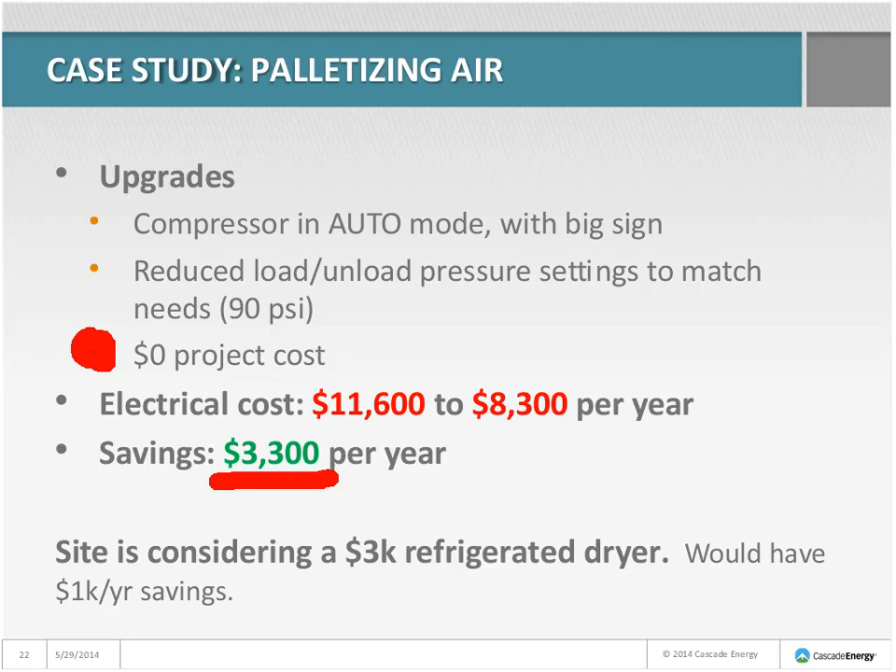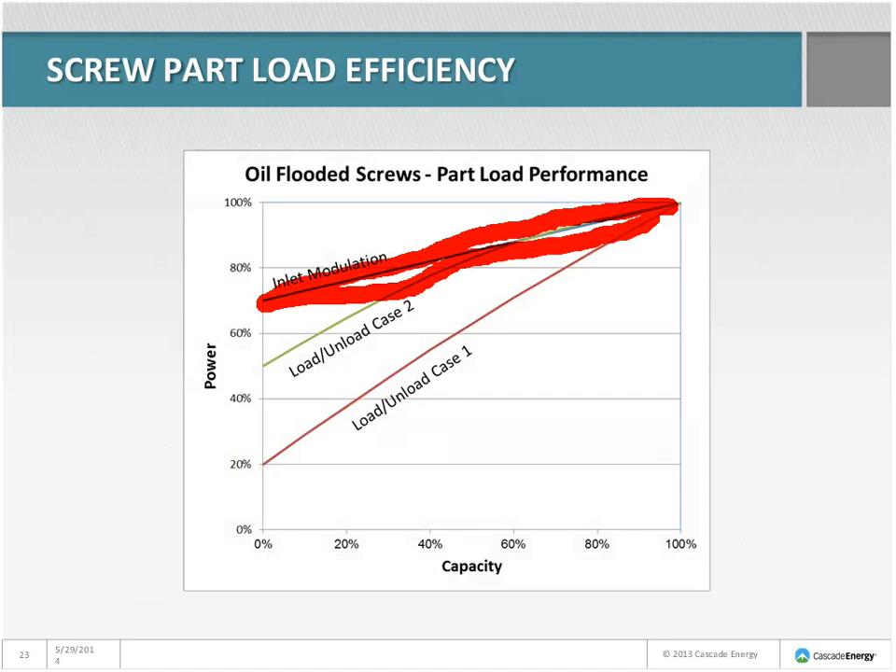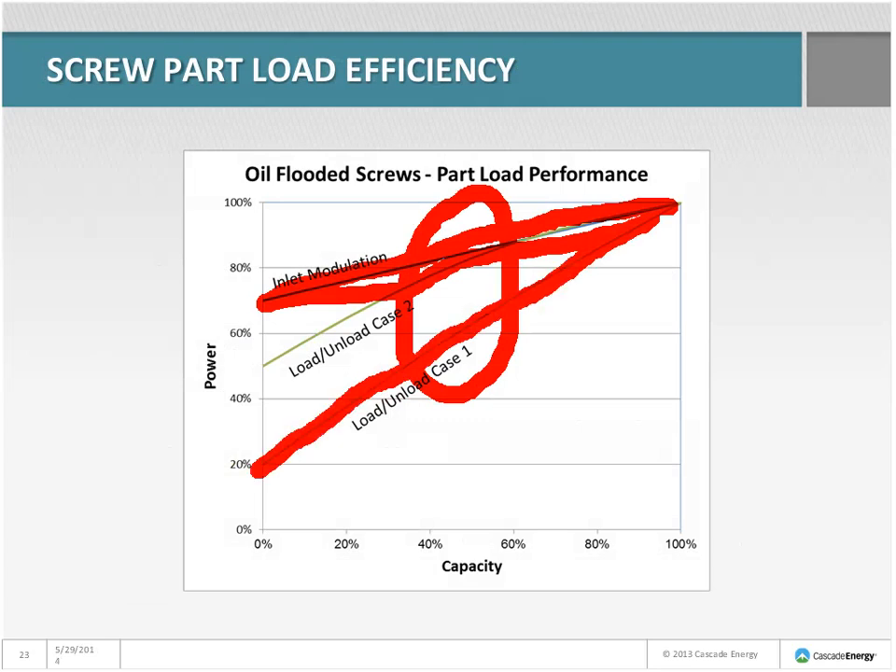These customers weren't interested in spending money but wanted to tune up the system. They put the compressor in automatic mode and posted a sign so operators knew: auto only. They reduced the load and unload pressure settings to match the palletizer's needs — about 90 PSI was sufficient, so they didn't need anywhere near 130 PSI. This cost no capital money, just operator time to read the manual, adjust settings, and test. It saved about $3,300 per year. They're also considering a $3,000 refrigerated dryer, which could save another $1,000 per year.